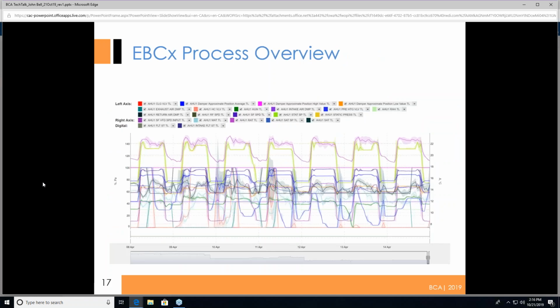All right, so this is just an overview of an air handler, the number of points that are on an air handler, and this conveys the amount of data. I think we all appreciate how much data is available. We don't utilize it nearly to its fullest, but if we look at it, this is just one air handler, right? 30 points at 5 minutes. That's 3.1 million points per year. Right, multiple air handlers, multiple systems. You start getting the gravity at which we're just not fine tuning or wringing that cloth out enough on our buildings.